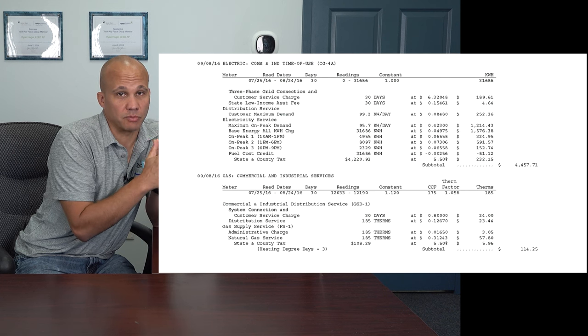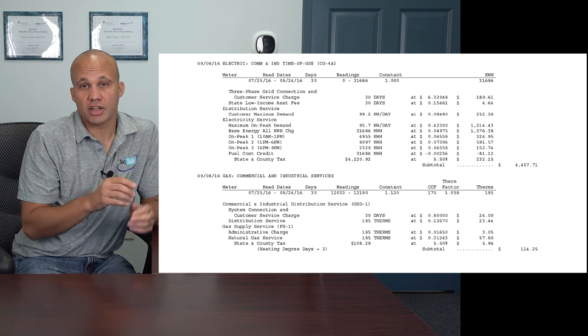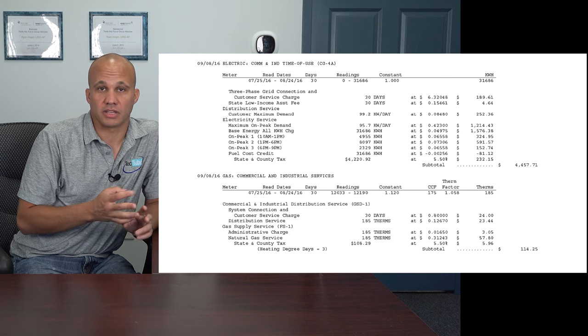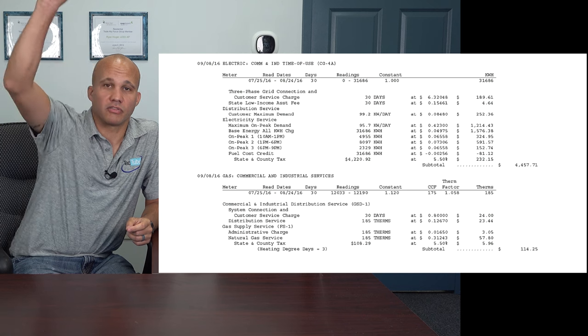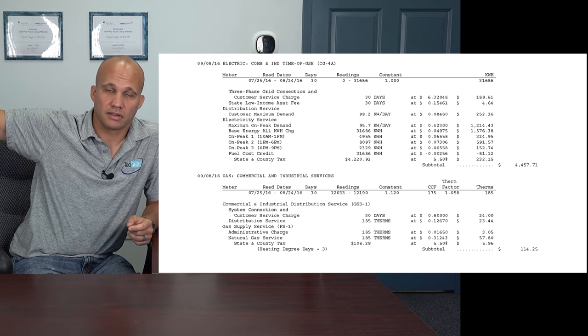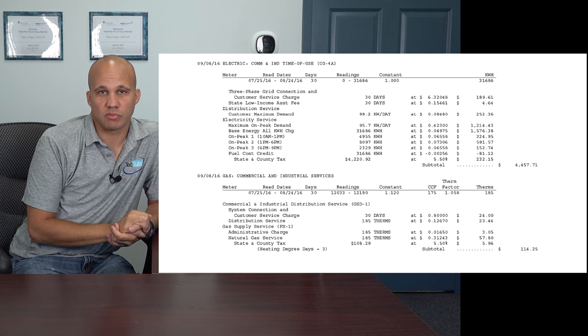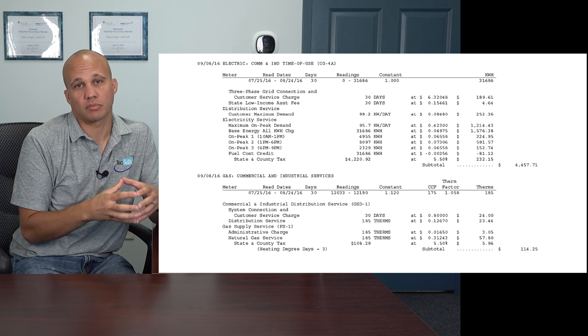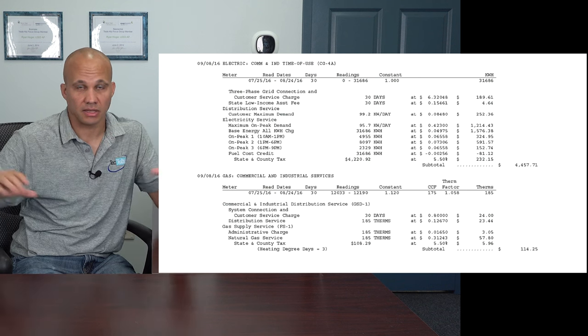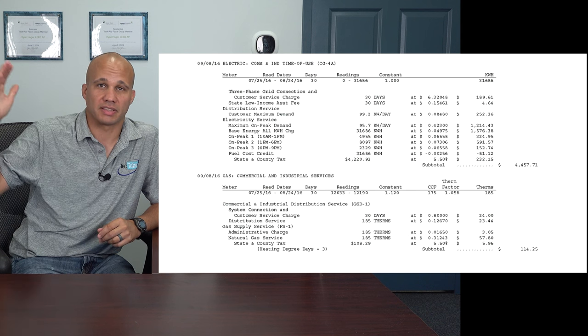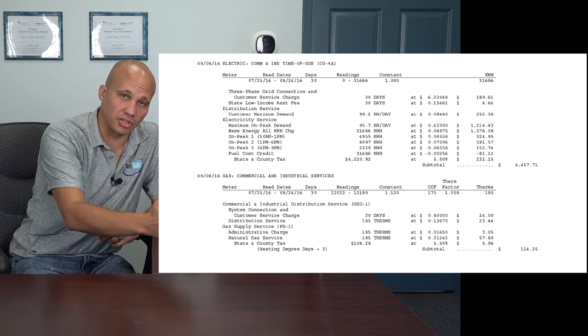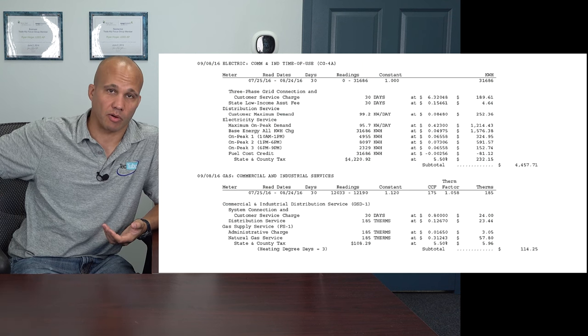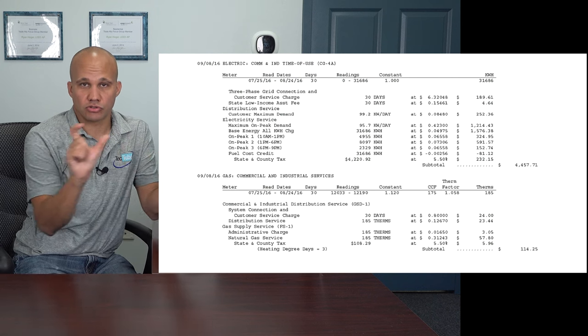In some buildings, that peak demand becomes way more important than the energy usage. As you turn on inductive loads like compressors, rooftop fans, and chillers, those things get a big inrush current spike and then settle off. If you get a lot of big spikes at the exact same moment, you'll get a pretty big demand charge. The utility charges the demand charge because that determines how big the grid needs to be — the line sizes in your neighborhood, the line from the transformer to your building — all dictated by peak demand versus actual energy usage.